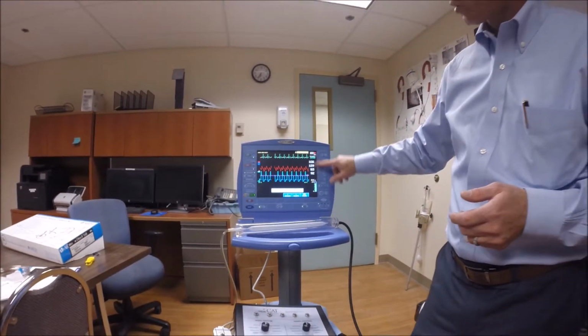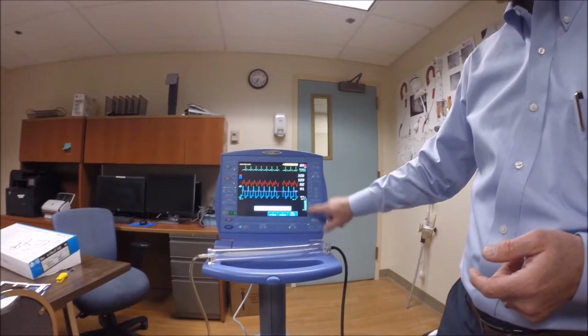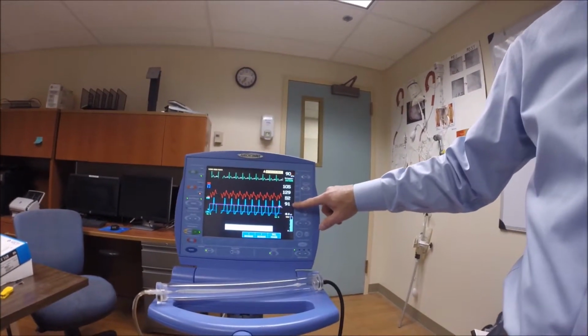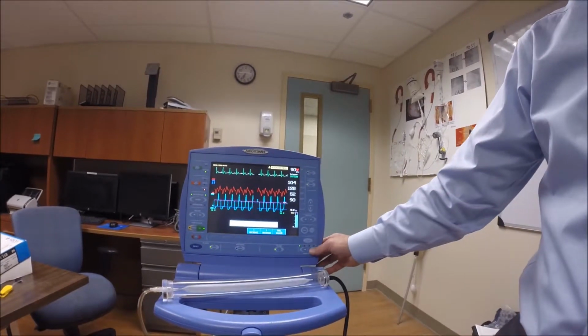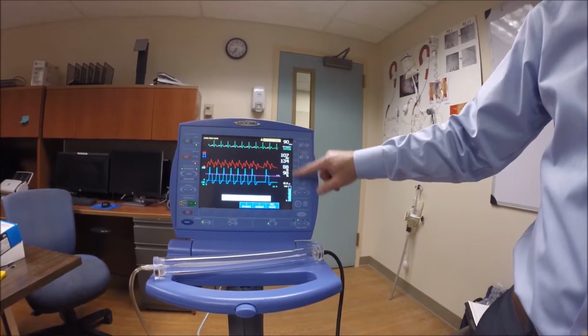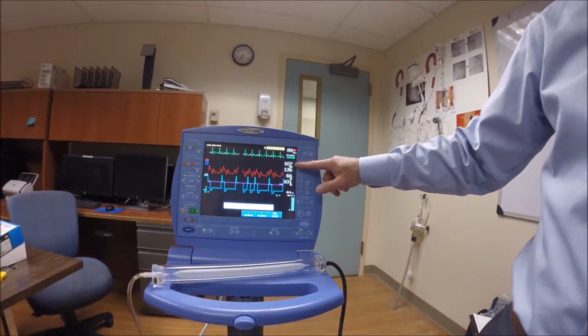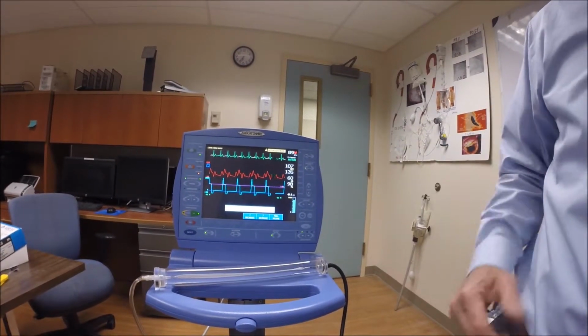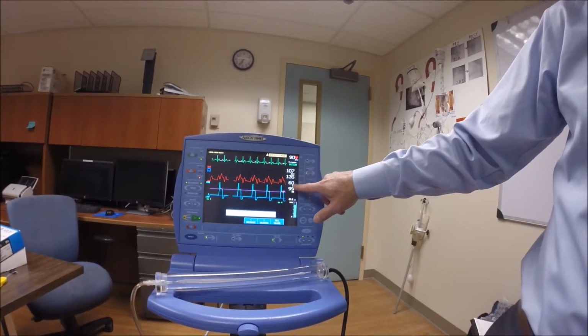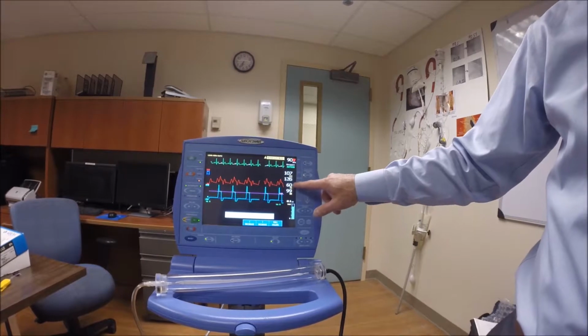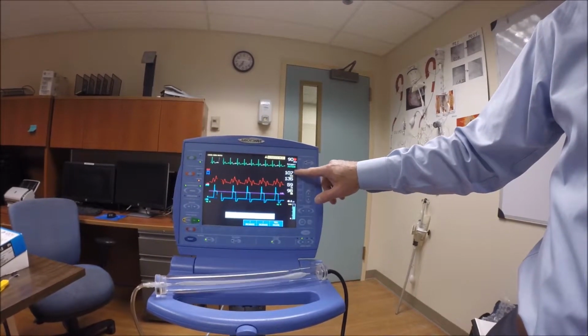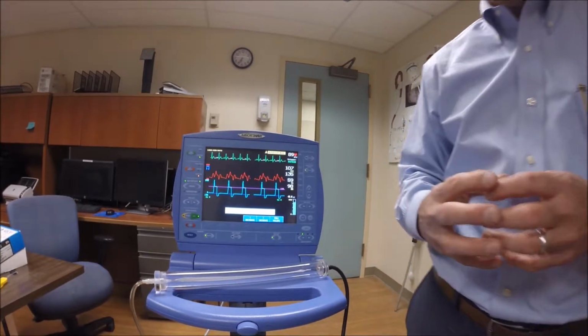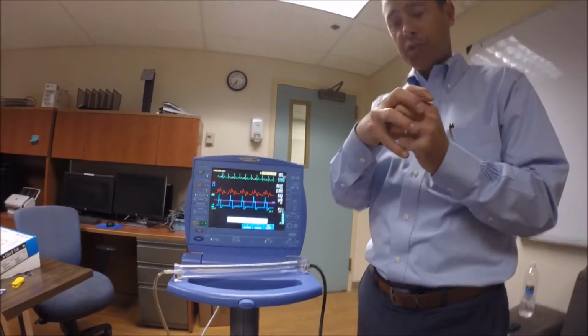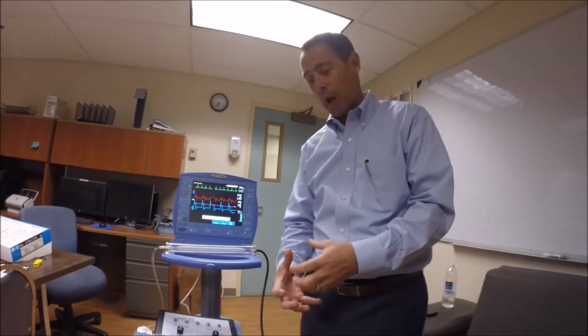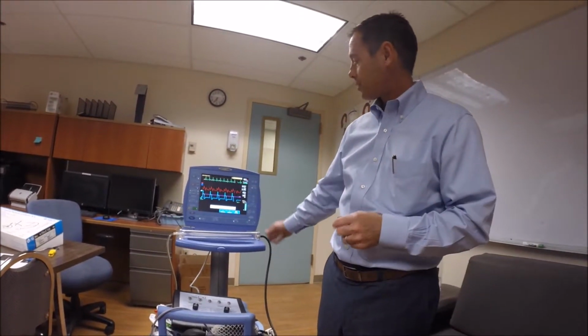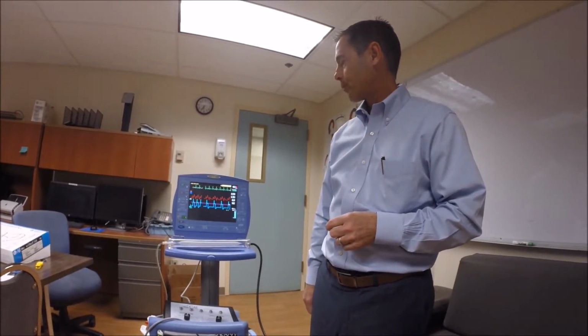Let's talk about our pressure readings over here. I'm in a 1-to-1 ratio, and all of these pressure readings over here are assisted, which makes sense. If I jump to a 1-to-2 ratio, I now have two sets of numbers. My big white numbers are my assisted pressures, and my little yellow numbers are my patient's actual pressures. And sure enough, my diastolic is 71 versus 60, and systolic 111 versus 107, which is exactly what balloon pumping is. It is not only more perfusion, but it's also that afterload effect, the pressure drop. So these are exactly what I want to see, and then I can go back to that 1-to-1 ratio.